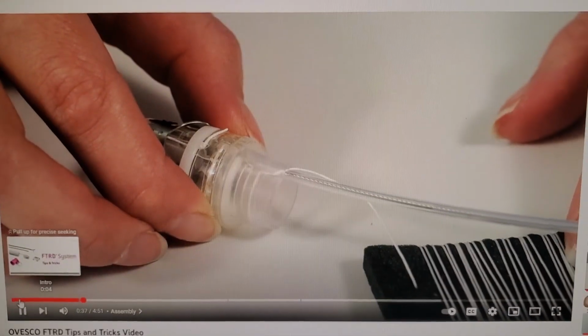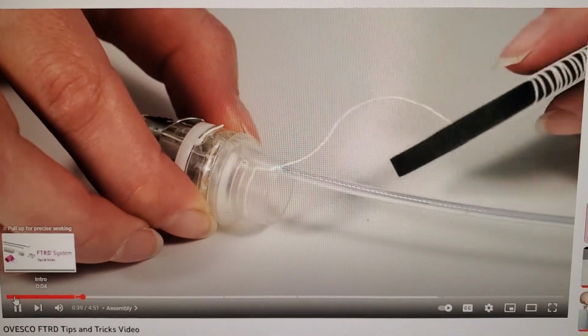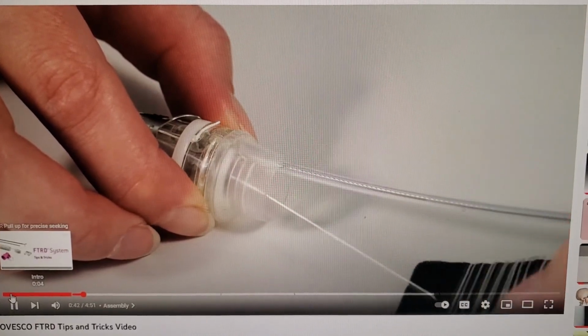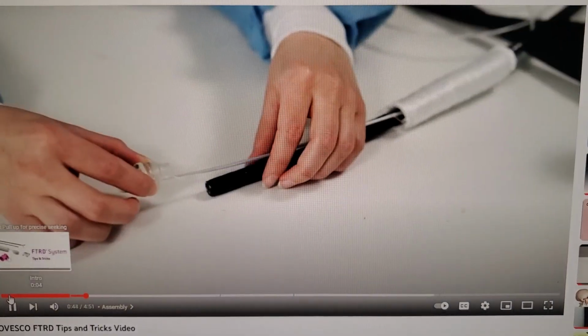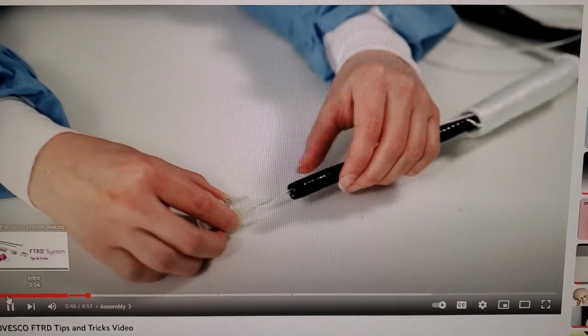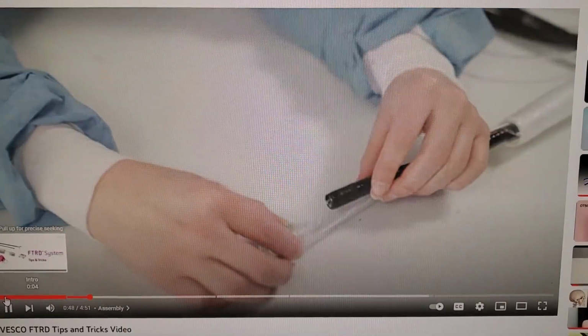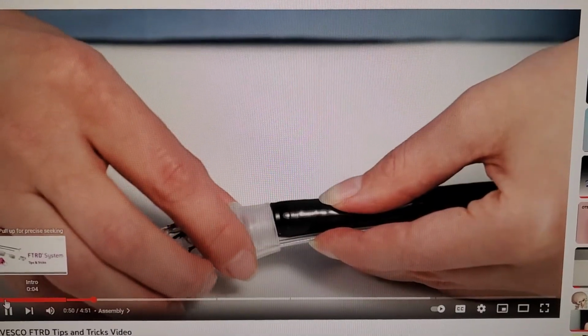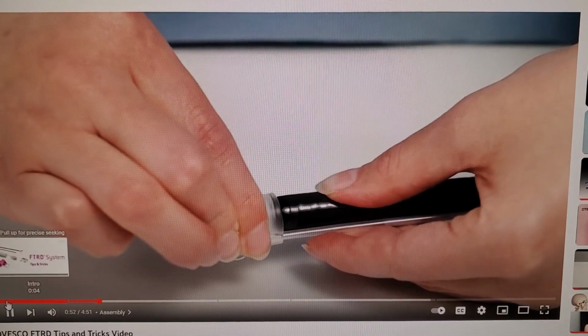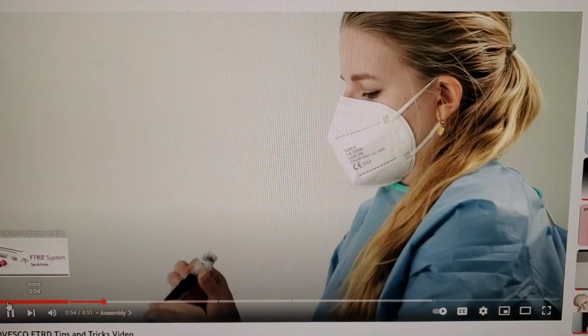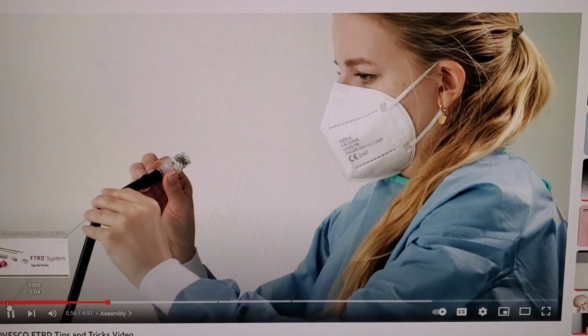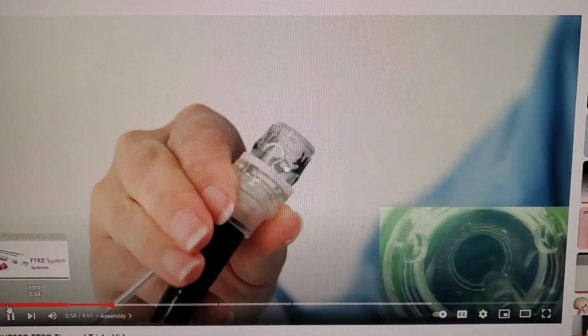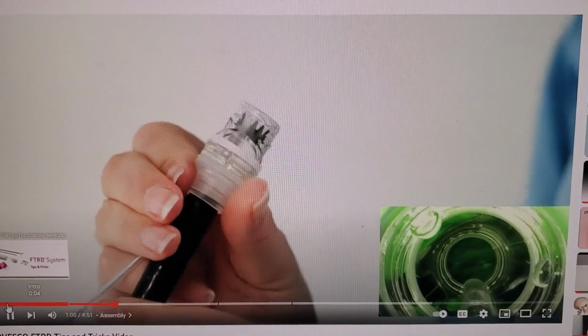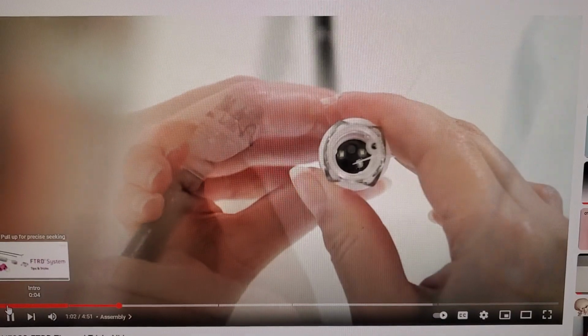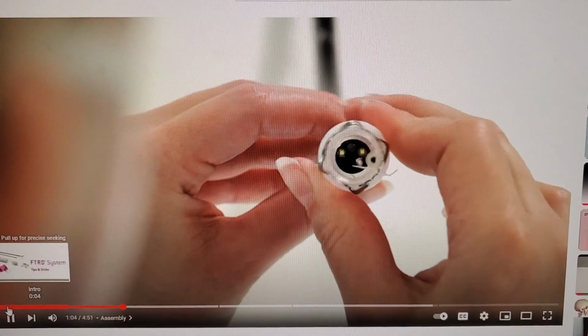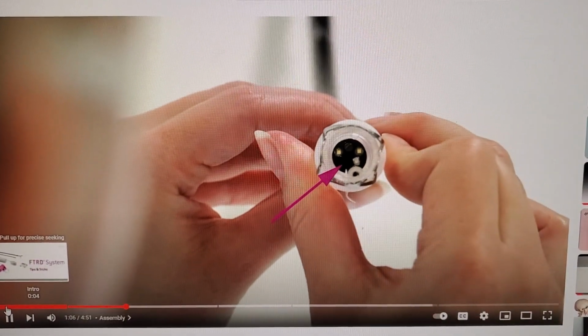Ensure that the release thread is not wound around the snare shaft throughout assembly. This can otherwise make clip application difficult or even impossible. To start, place the application cap only lightly on the endoscope tip. The release thread must enter the working channel vertically and not conceal any of the endoscope functions. The working channel should be located directly next to the snare shaft tube, so that the working channel outlet remains clear.